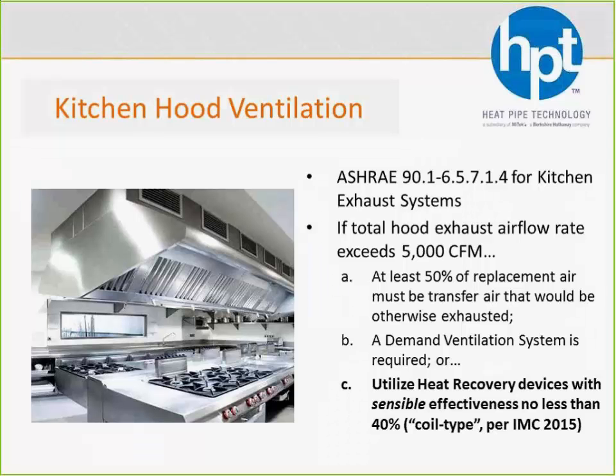So ASHRAE standard 90.1. One of the things it gets into is kitchen exhaust systems. And actually, if the total airflow rate that's being exhausted out of a kitchen exceeds 5,000 CFM, ASHRAE 90.1 requires that you do one of three things. One is that at least half of that replacement air is transferred air that would otherwise be exhausted, so that's an option you can do.